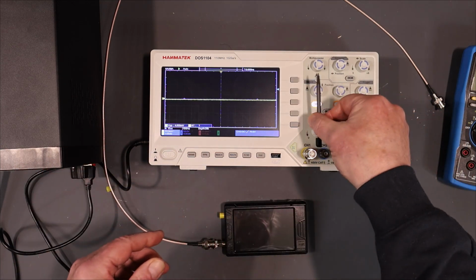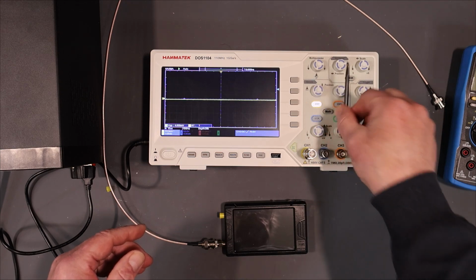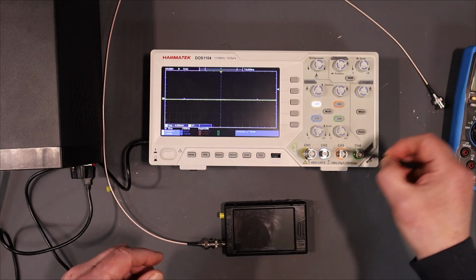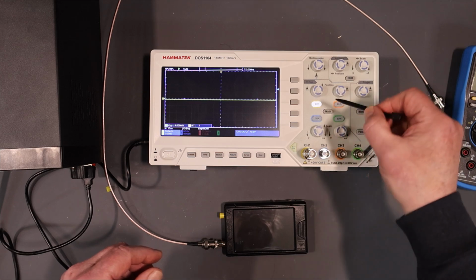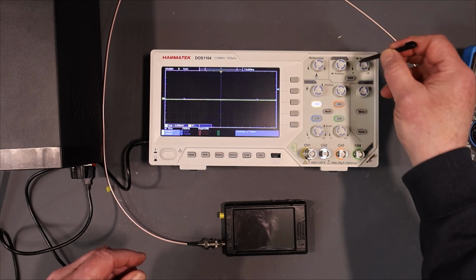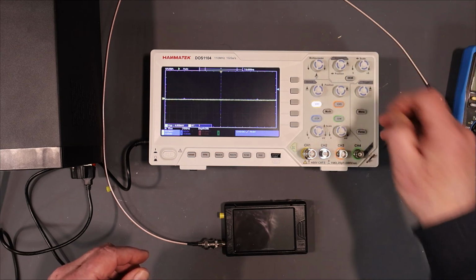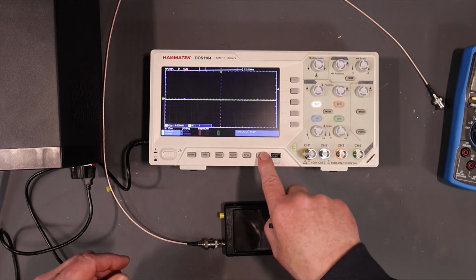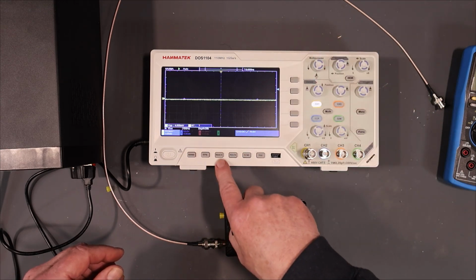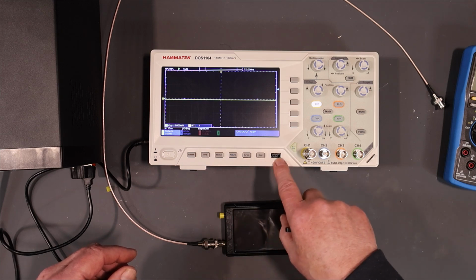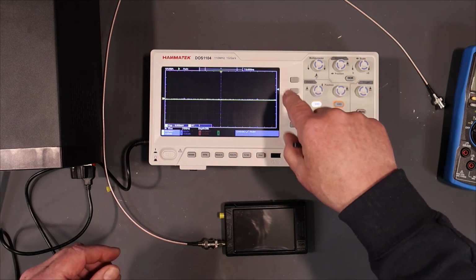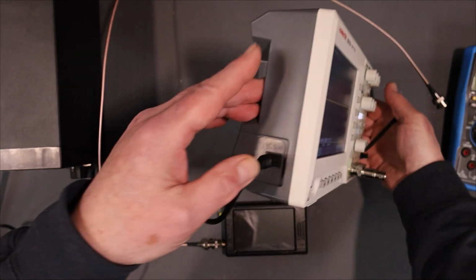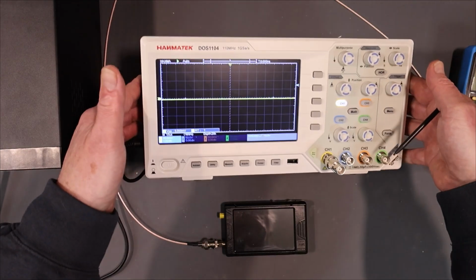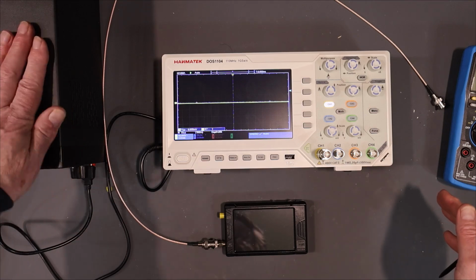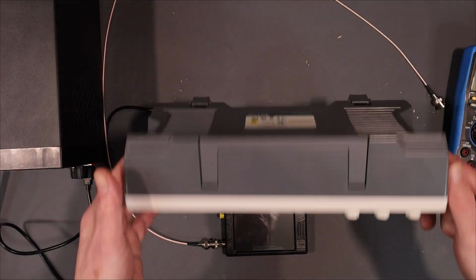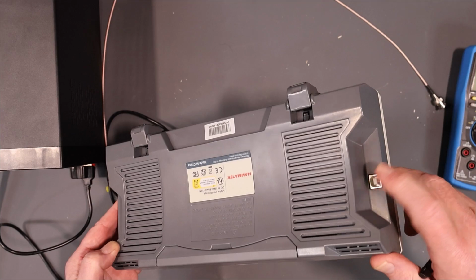It has one nice feature in that you can have two vertical controls on at the same time. That's really good for just doing two channel stuff. You don't have to switch back and forth between them. It's got the horizontal, it's got your trigger, and it's got your multifunction knob. All your different menus are available down here. Auto set, utility, measure, acquire, cursor, and copy. And then it's got buttons you can select from within the menu. So you'll see as we bounce through it. It powers off DC, 5 volts DC, so that's handy. Right now I have it being powered off our B-side power supply here. And on the back, there's also a USB output.